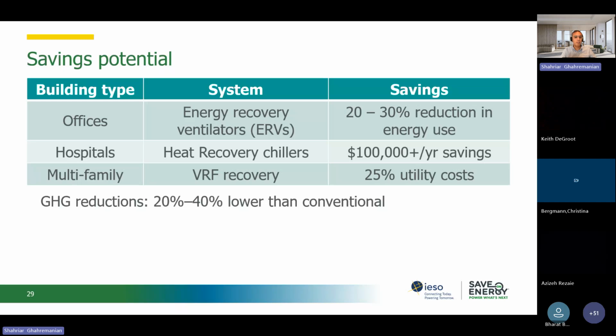Examples of heat recovery: for an office building or residential building, an energy recovery ventilator is really good. You can decrease your energy use by 20 to 30%. In a hospital, heat recovery chillers are, to me, a must have. It's not something that is just good to have. Today it is a must because that technology is available to us. It has a cost to install, but the saving is huge. The saving can be more than $100,000 per year.